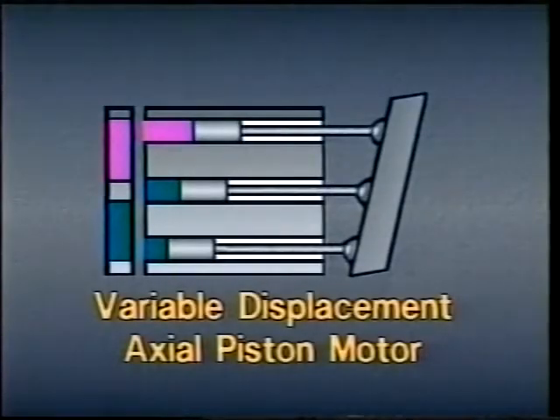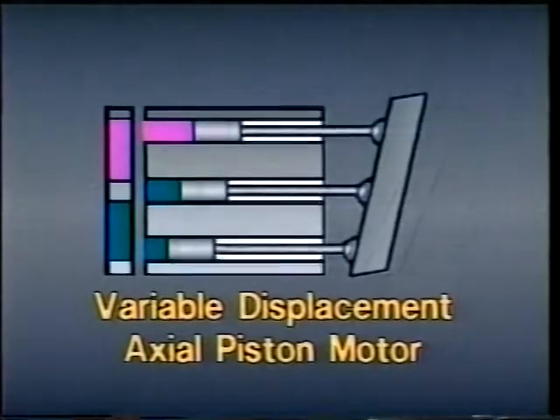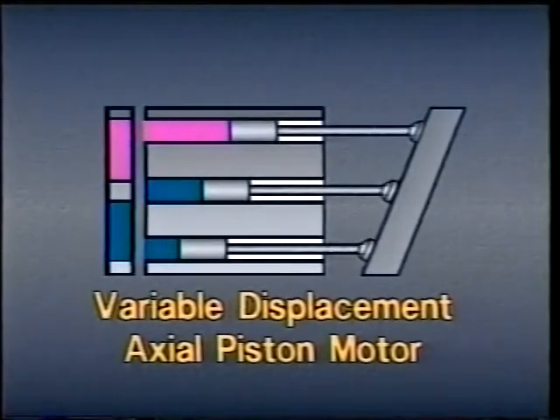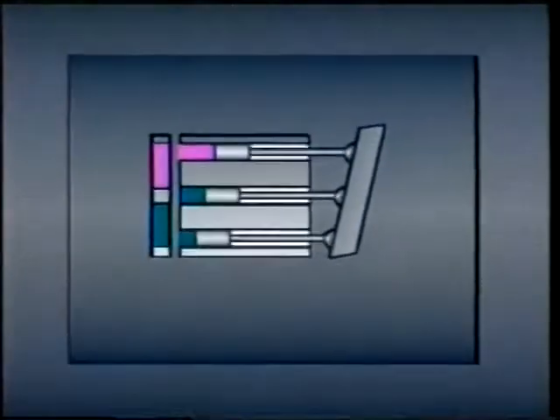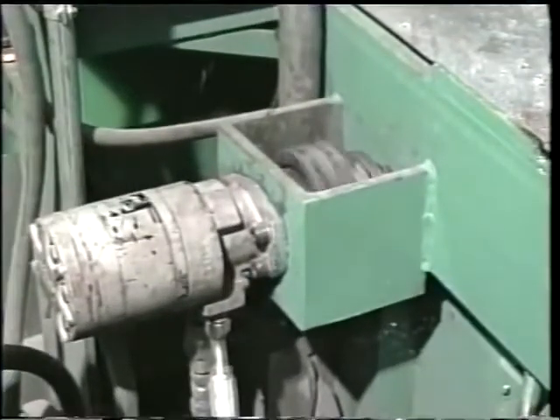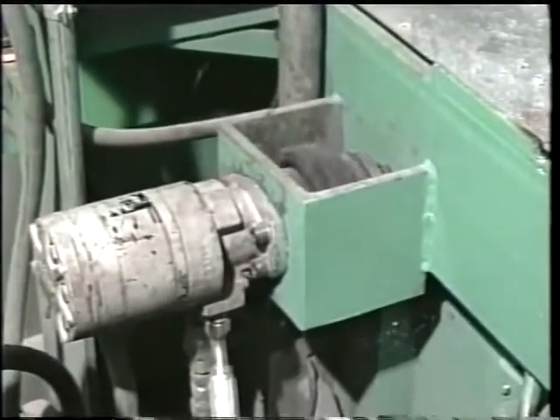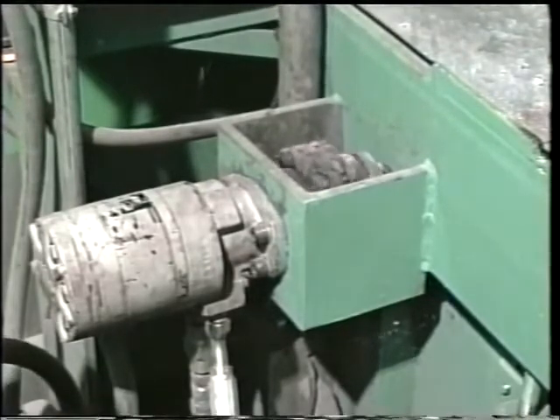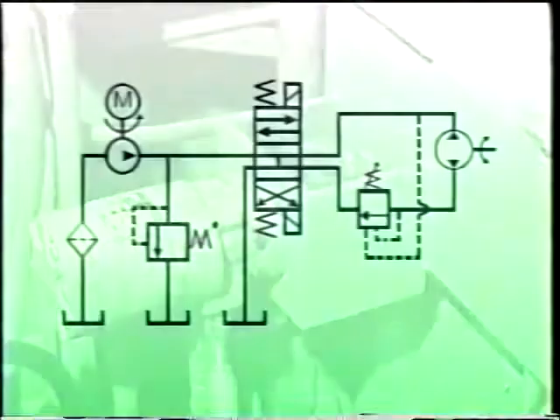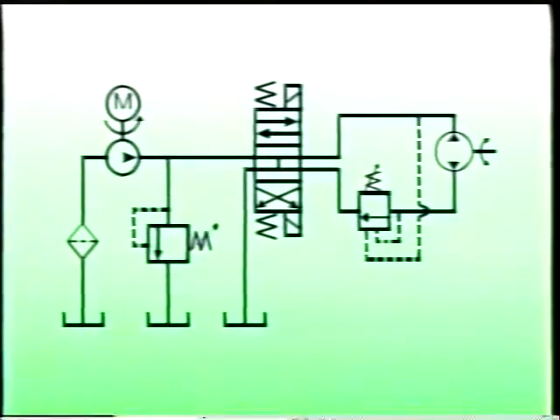When torque must be regulated at different speeds, a variable displacement piston motor can be used. Increasing the angle of the swash plate increases the displacement and the torque, while decreasing the angle decreases the displacement and the torque. In addition to regulating the speed and torque of motors, it is often necessary to slow down a motor and its load. Sometimes a motor is simply allowed to coast to a stop, and sometimes mechanical brakes are used, but hydraulic motors can also be dynamically braked.